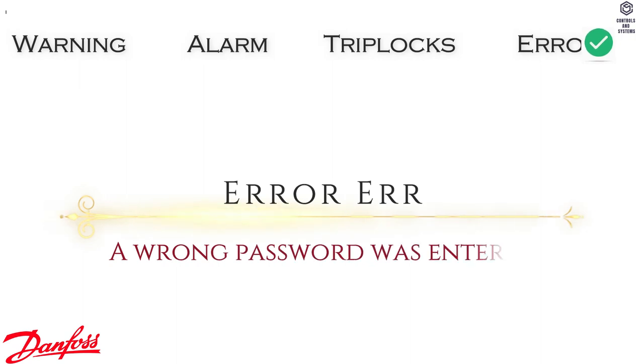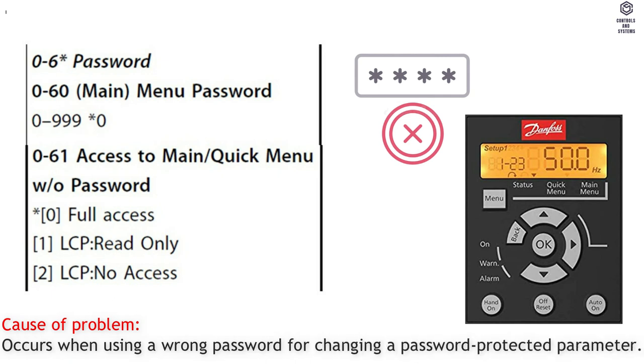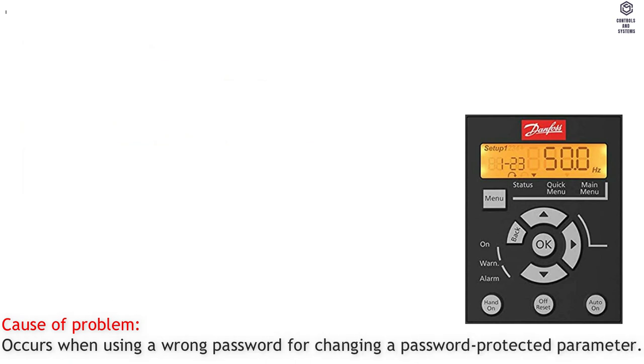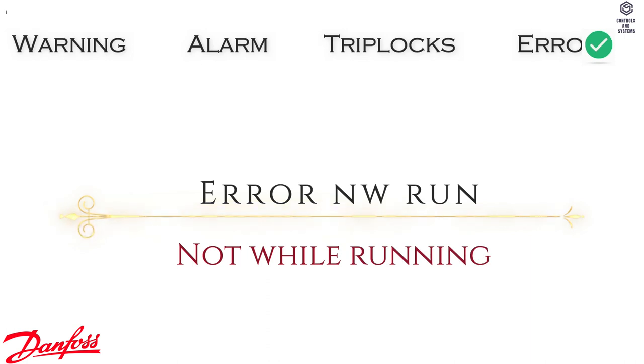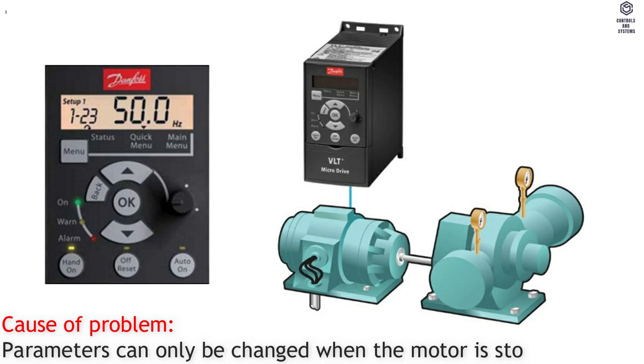Error ERR: A wrong password was entered. Cause of Problem — occurs when using a wrong password for changing a password-protected parameter. Error NW Run: Not While Running. Cause of Problem — parameters can only be changed when the motor is stopped.